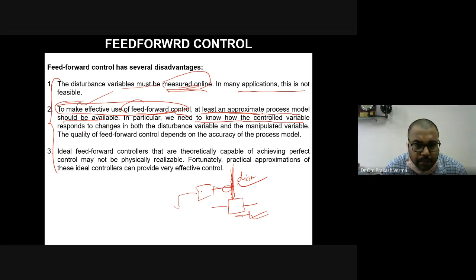So to make effective use of the feed forward control, this is the one disadvantage we already discussed. For effective feed forward control, you have to identify all the disturbances, or you can say you have to model the process in an exact way. At least an approximate model should be available. If your model is not available, then you are not able to measure that disturbance, or you can say the feed forward controller will not work properly. So in particular, we need to know how the control variable responds to changes in both the disturbance variable and the manipulated variable, right? So the quality of the feed forward control depends on the accuracy of the process model, as I have already said.